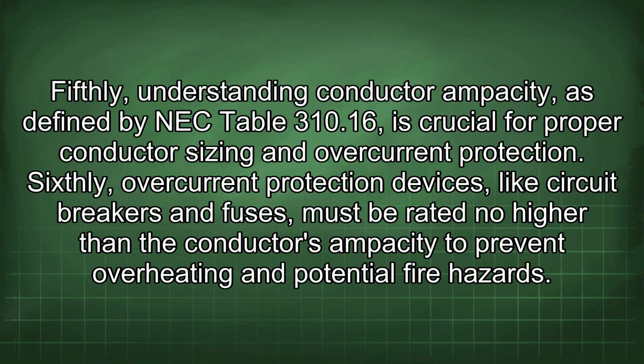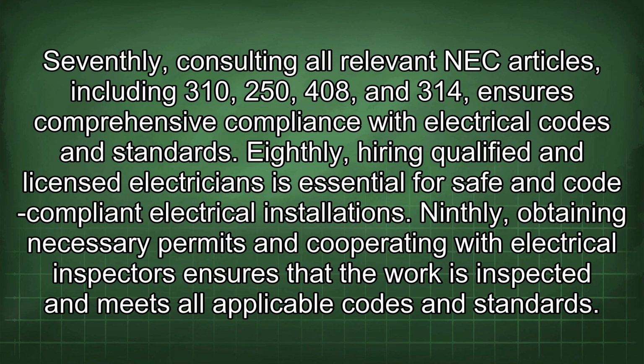Fifthly, understanding conductor ampacity, as defined by NEC Table 310.16, is crucial for proper conductor sizing and overcurrent protection. Sixthly, overcurrent protection devices, like circuit breakers and fuses, must be rated no higher than the conductor's ampacity to prevent overheating and potential fire hazards. Seventhly, consulting all relevant NEC articles, including 310, 250, 408, and 314, ensures comprehensive compliance with electrical codes and standards.